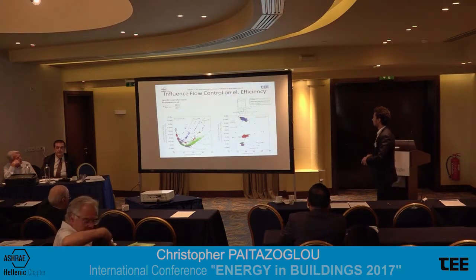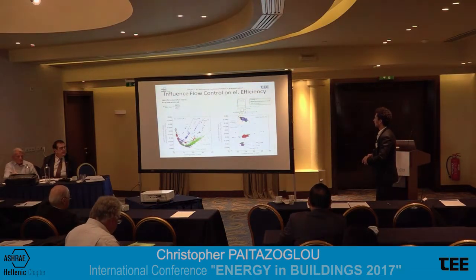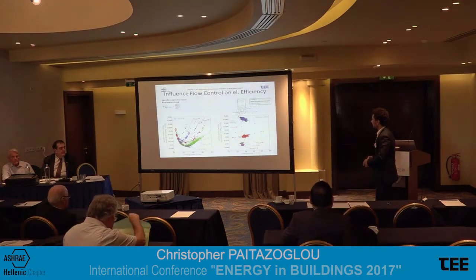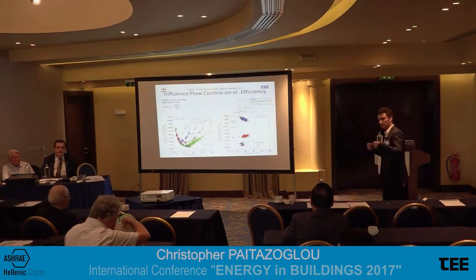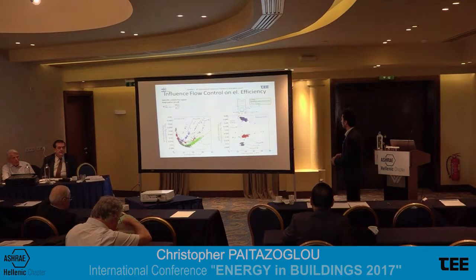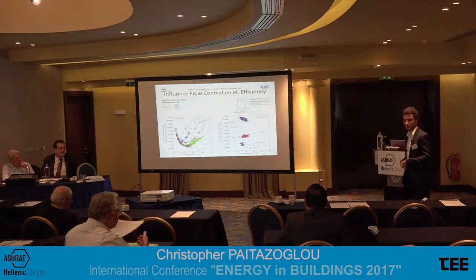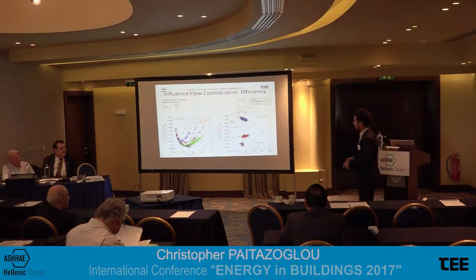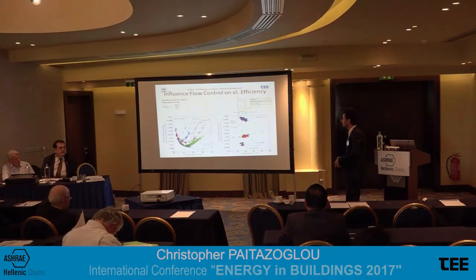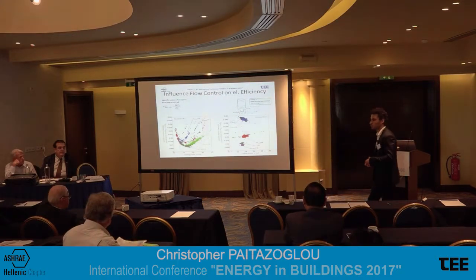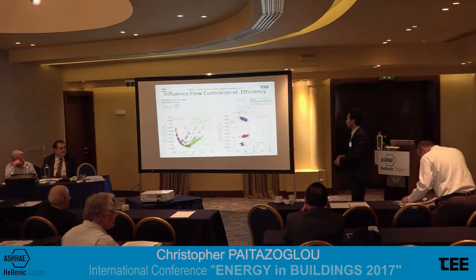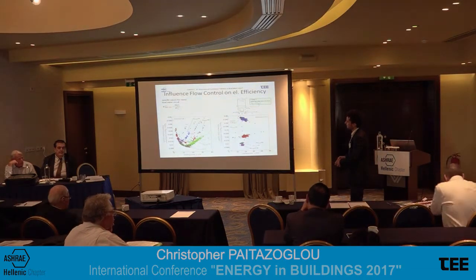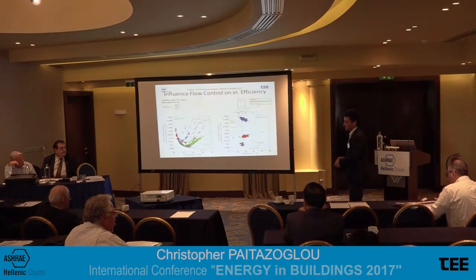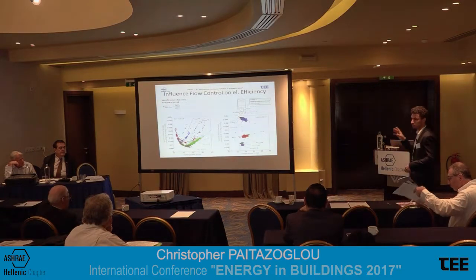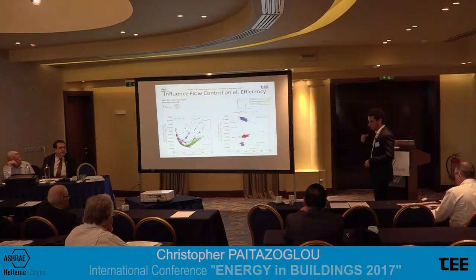So we see here that the black dots indicate that the strategy is inactive, and once the strategy is activated and we increase the temperature difference, thereby decreasing the volume flow in this pump here, we dramatically decrease the specific energy consumption in this circuit. The same can be seen here, where we have a somewhat more fluctuating cooling load, but in the end the outcome is the same. It follows the characteristic of the cooling load in the site a little more, but nevertheless we see that with increasing temperature differences in the cooling water circuit, the specific electrical energy consumption in the circuit decreases again. So it's a very promising strategy. Other strategies are also quite promising.